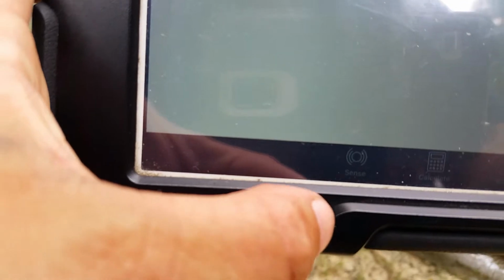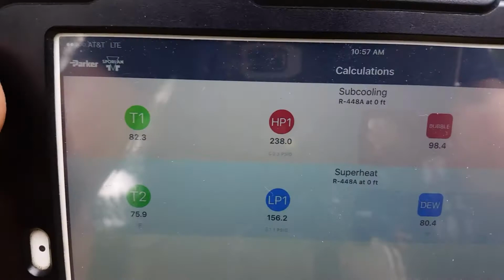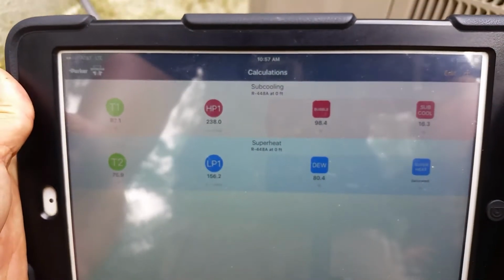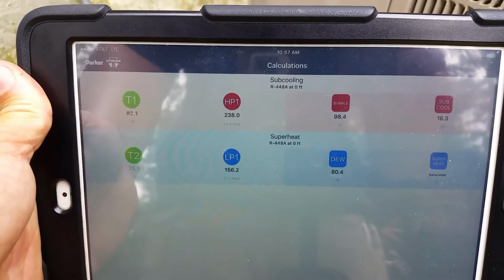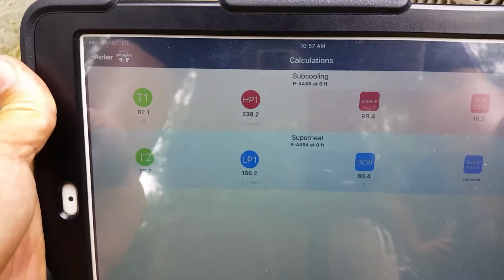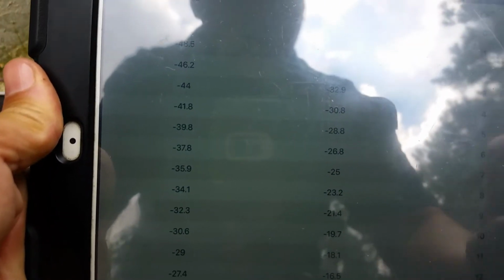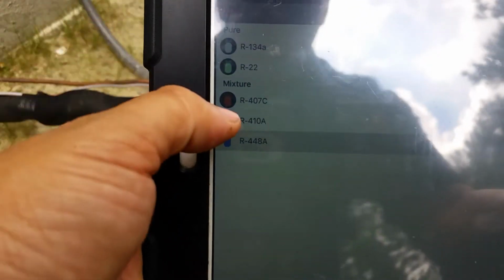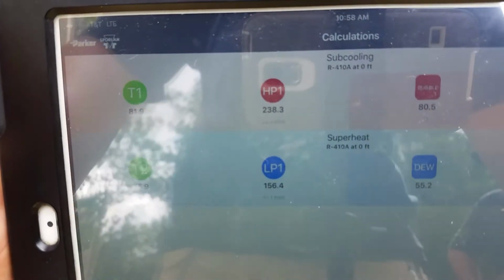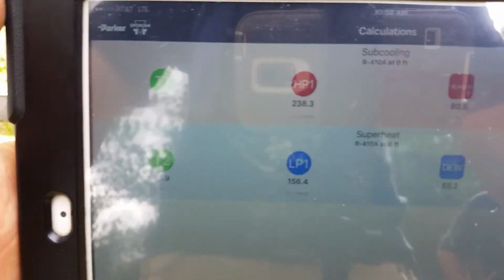And if you go down to the bottom, not sure how well you're going to be able to see, but there is an icon that says calculate. If you click that, it's going to bring up the screen that most everybody's familiar with in this app. It gives you your superheat, subcooling, pressures, T1 and T2. And the next icon over at the bottom, you can select your refrigerants. So we'll go to 410A. Go back to calculate. So now we're on 410A, and we are ready to turn the unit on and check.